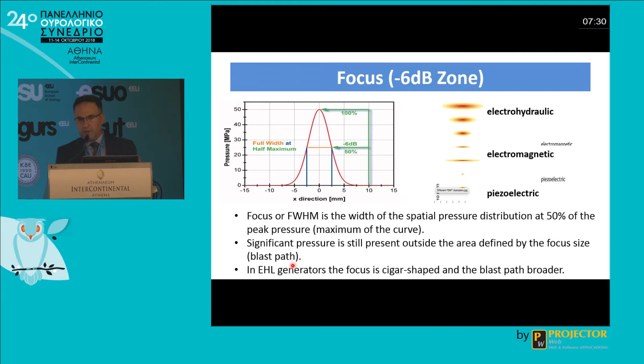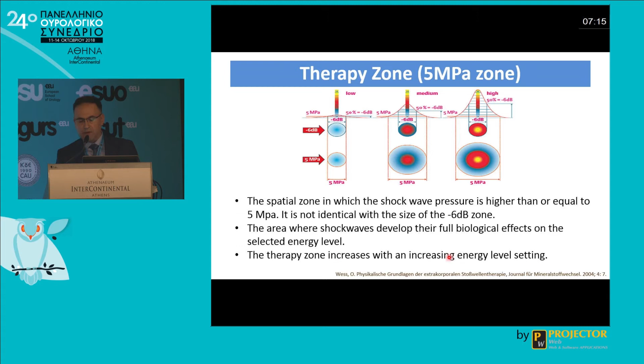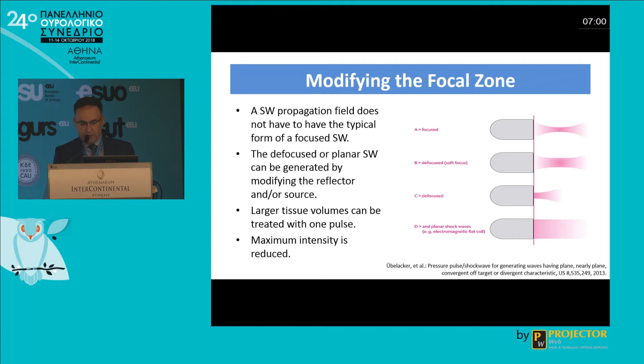The focal zone is the area where the pressure is over 50% of the peak. But most important is the therapy zone, which is the area where the full biologic effect is present. This is not identical with the size of the -6 dB zone and increases with an increased energy setting. But we don't need to have a typical form of focused shock waves. We can modify it by modifying the reflectors and the sources, and we can produce wider beams that can cover larger tissue volumes with one pulse.